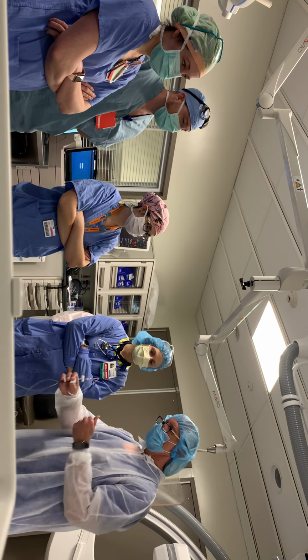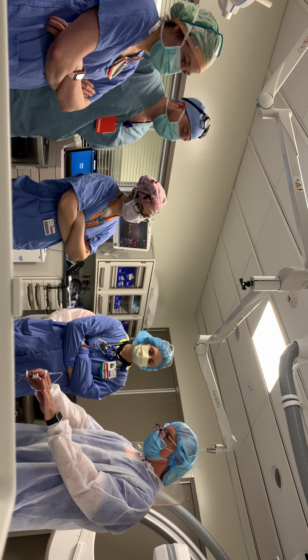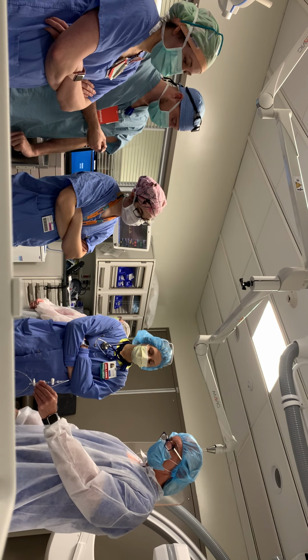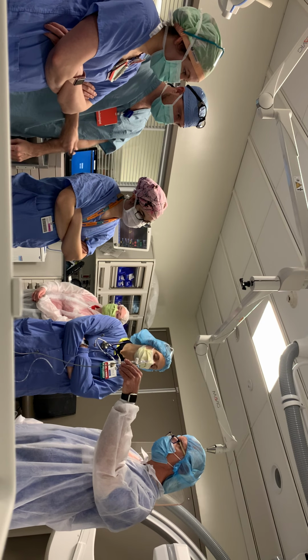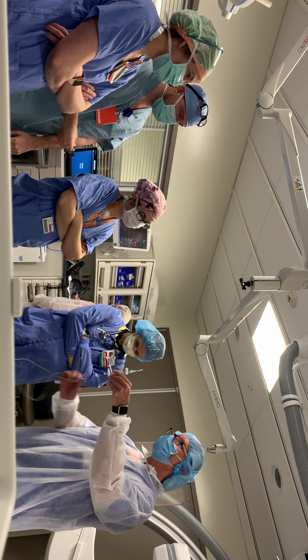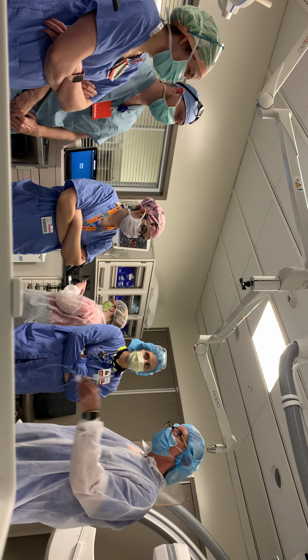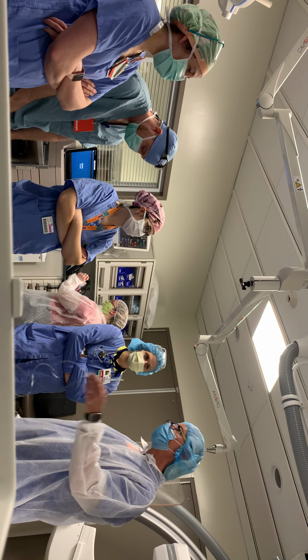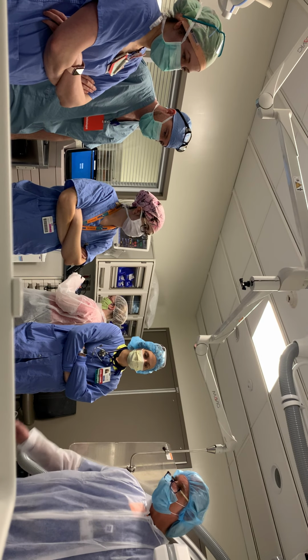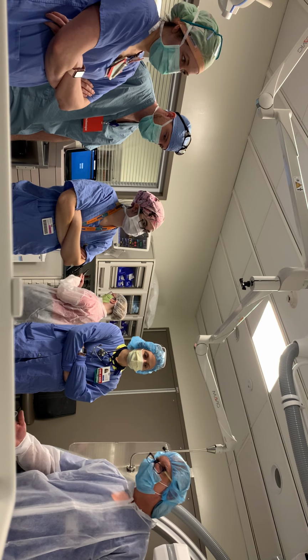If during a case, this is of course just a regular pole-mounted transducer, so they fix those at heart level. They usually set it to this port. During a case, while connected to the patient, if you're measuring the pressures, and you actually go over and physically raise the transducer, their pressure is going to drop. It's not really dropping. It's dropping because the weight of the fluid is actually a negative to the patient's pressure. So it's a dynamic zero. Hydrostatic is a dynamic zero. It changes when you change things. So, do you have to re-zero? Probably not. Does it hurt? No. It's quick, it's fast.